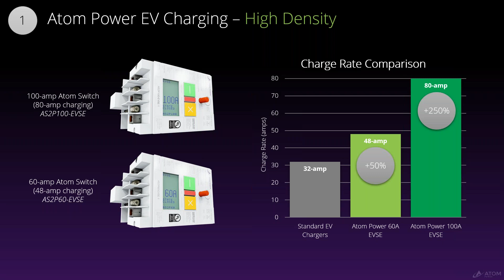On top of the less risk of the panel being inside the building as opposed to outside, since the power is controlled at the circuit breaker level, there's no hazardous voltage at the charger, at the pedestal or the wall box when it's not in operation. That's big, because when a vehicle's plugged in, it can't move, so the highest chance of someone running into it is when they're backing in or pulling out. During that time, there is no voltage at the pedestal, so it's very safe.